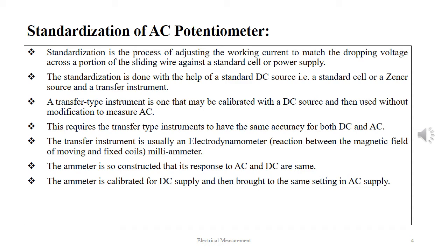The standardization is done with the help of a standard DC source, i.e. standard cell or a Zener source, and a transfer instrument. A transfer-type instrument is one that may be calibrated with a DC source and then used without modification to measure AC.